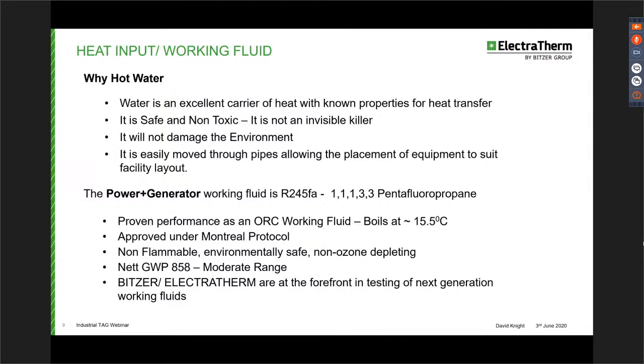Our working fluid is R245fa, which has a proven performance as an ORC working fluid, boiling at 15.5 degrees centigrade. It's approved under the Montreal Protocol. It's non-flammable, environmentally safe, non-ozone depleting. It's in the moderate range of GWP. However, we are aware that there's action now on GWP, and we are at the forefront of testing the next generation of working fluids. What we're looking for is an ultra low GWP, basically less than 1, and performance similar to what we get with the 245fa, and availability.